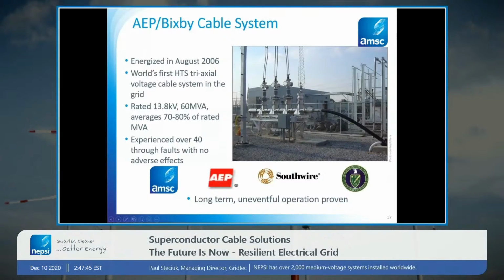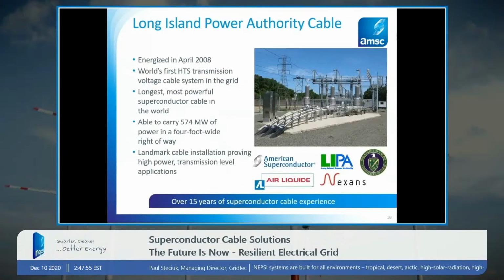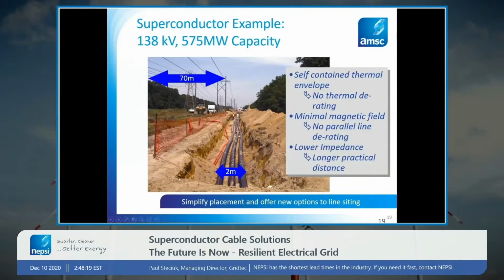So this was the first demonstration, getting to be 15 years ago, where we first demonstrated this technology in a US substation at distribution voltage. 2 years later, in 2008, we demonstrated 138 kV, a transmission voltage at LIPA in Long Island in New York. Again, part of the Department of Energy program to demonstrate this technology. This was a 574 megawatt cable. And just to give you an idea of why this technology is attractive, in this single 2 meter wide underground corridor, we were able to move the same amount of power as this 70-meter wide overhead corridor.